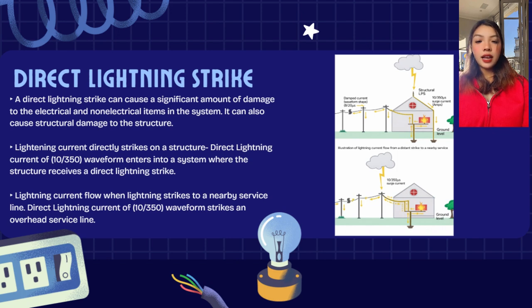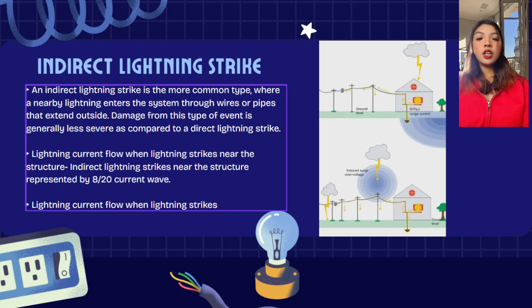So, the next slide is the indirect lightning strike. This strike is near the structure, not directly on it. The surge enters through power lines, pipes, and communications cables, and uses the 8/20 waveform. The effects of this are less severe than a direct strike, but more common and still damaging. This is the most frequent cause of surge-related damage in electrical systems.